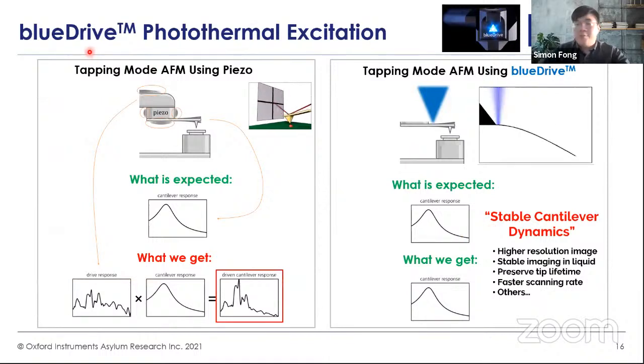So here is a little bit of explanation of what blue drive is. In conventional tapping mode, as you can see here, the tip taps across the sample. This tapping is generated by a shake piezo. A current passes through a piezo piece, and the piezo actuates the cantilever attached to it at a resonance frequency.